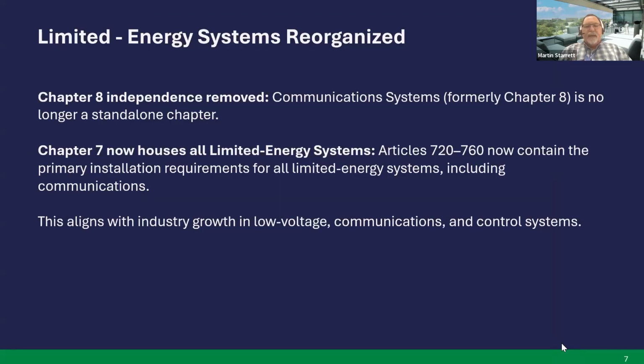Next slide, please. So one of the things that you'll see in the 2026 code is the limited energy systems are reorganized. Chapter 8, independence is removed. Communication systems is no longer a standalone chapter. Chapter 7 now houses all limited energy systems, what we would call kind of a low voltage. So Articles 720, 760 now contain the primary installation requirements for all limited energy systems, including communications. This aligns with industry growth in low voltage communications and control systems. Next slide.